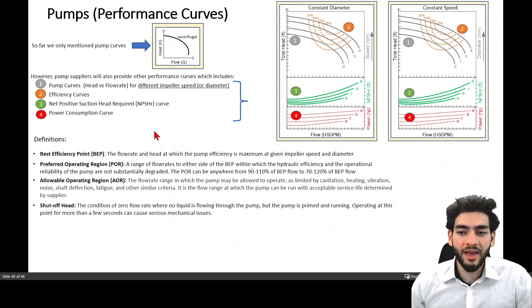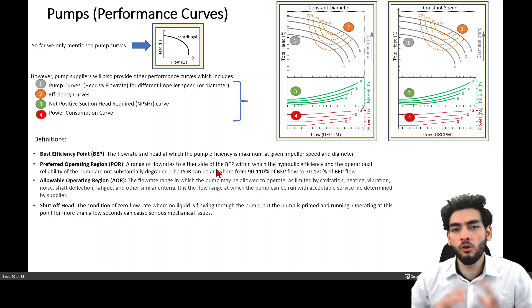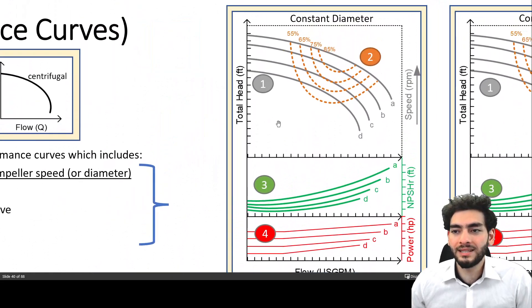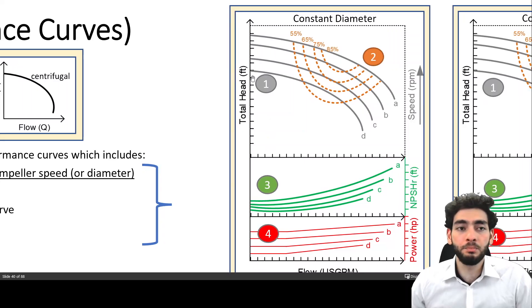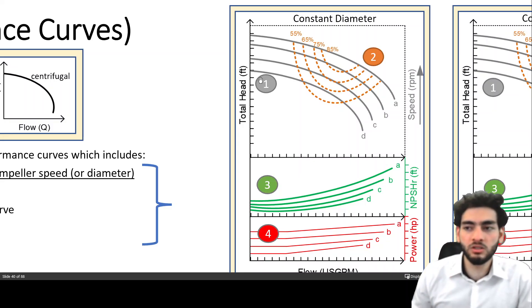The shutoff head is a condition of zero flow rate where no liquid is flowing through the pump but the pump is primed and running and so operating at this point for more than a few seconds can cause serious mechanical issues. So let's imagine that the pump is turned on but there's a valve that's closed at the discharge of the pump.